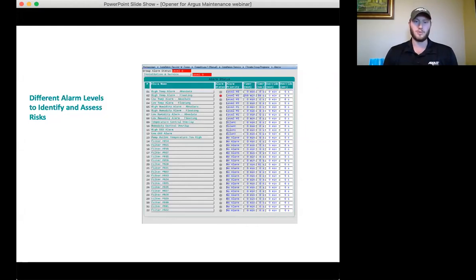But the other thing you can also do is use something as simple as a current switch, which basically tells you if there is current or no current in that piece of equipment. And you can tie that into a critical alarm. Environmental control systems have the ability to do different things when you get alarms. Sometimes alarms just pop up on the screen. Sometimes an alarm can send you a text message. And sometimes alarms can be automated to send you essentially a robocall. So once you understand what your critical pieces of equipment are, you can tie that into a critical alarm, something that would likely send you a phone call, whether it happens at 2 o'clock in the afternoon or 2 o'clock in the morning.